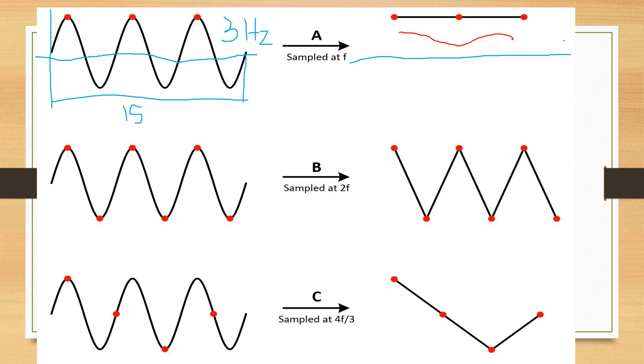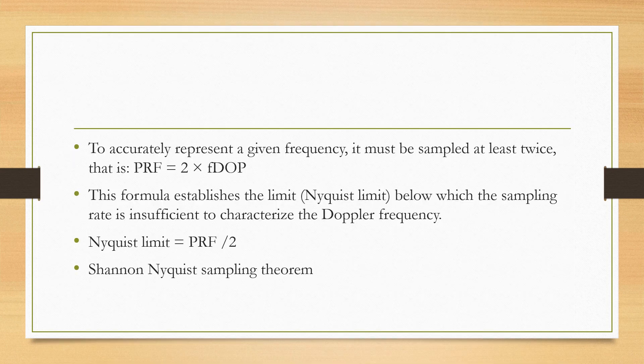The Nyquist Limit is the maximum frequency that can be sampled properly through that Doppler. To accurately represent a given frequency, it must be sampled at least twice. For example, for a four hertz signal, the minimum sampling rate needed to recreate the original is eight hertz — PRF equals two times the signal frequency. If the Pulse Repetition Frequency is 10, the Nyquist Limit is up to five hertz. The Nyquist Limit equals Pulse Repetition Frequency divided by two.